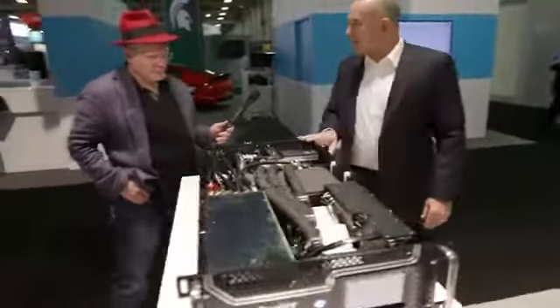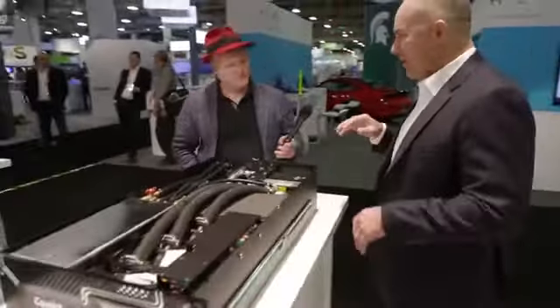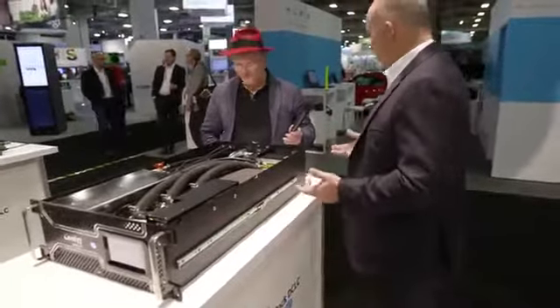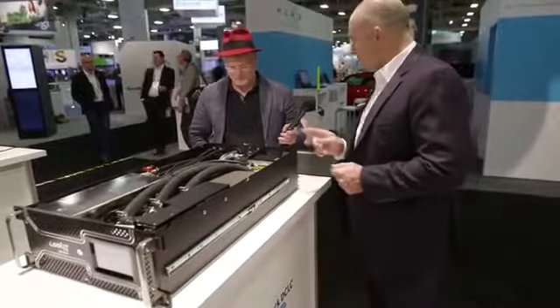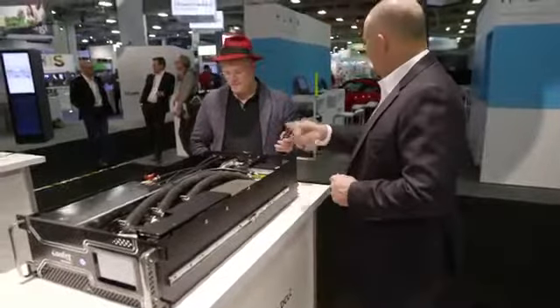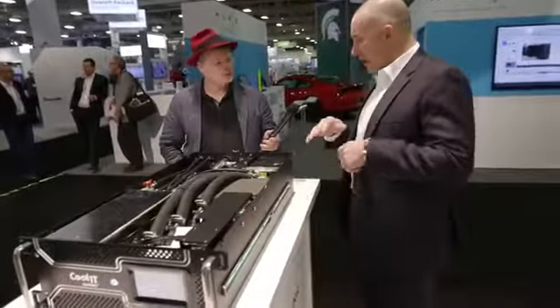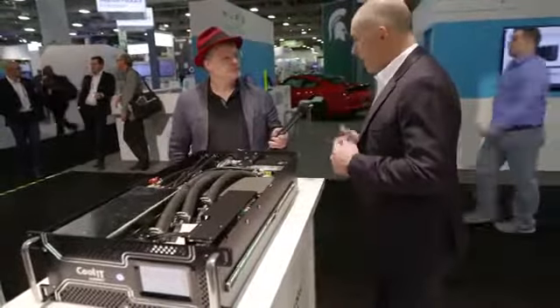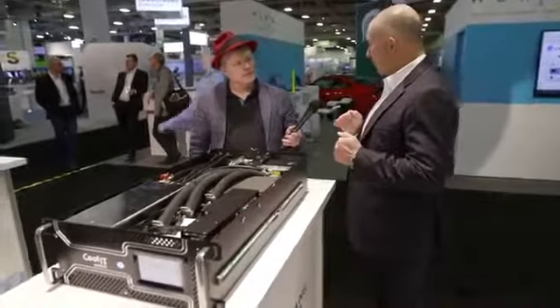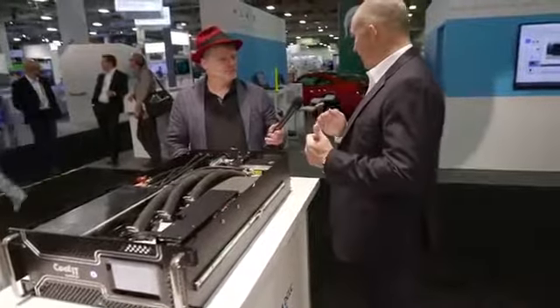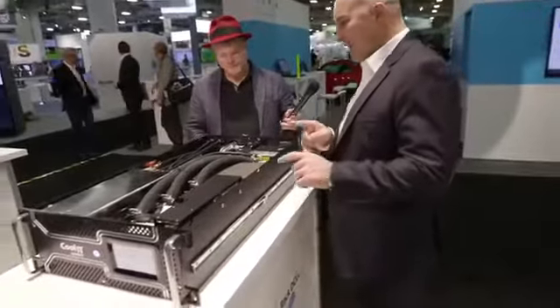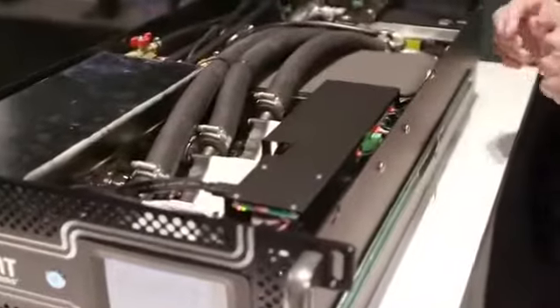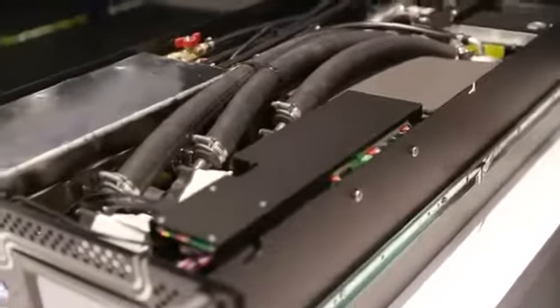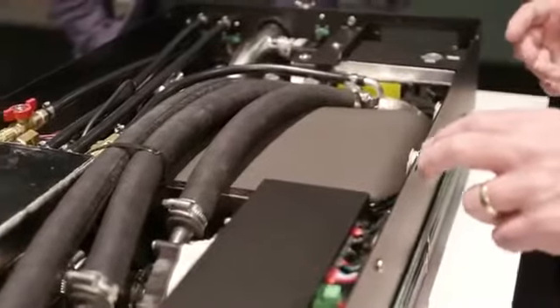This is the CHX80. Now, this is a featured up version as well. So on the CHX40, we had redundant pumping, but they were in series, right? So it did have a backup pump, but you would have slightly degraded flow if you were to have one fail. What we've done instead with this model is we actually have 3 pumps that are configured all in parallel, which gives us N+1. So only 2 of them will be running at any given time.